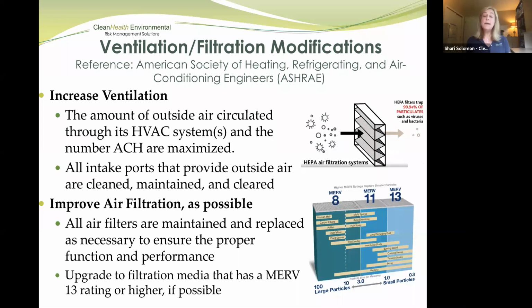What ASHRAE recommends is from an average of 1 to 2 air changes per hour, more so in a traditional type of office space, for example, up to 4 to 8. So I'm sure if I have any facility engineers on the call, they are shaking their heads because the cost benefit analysis of energy efficiency and of these increased ventilation requirements are potentially at odds with each other.